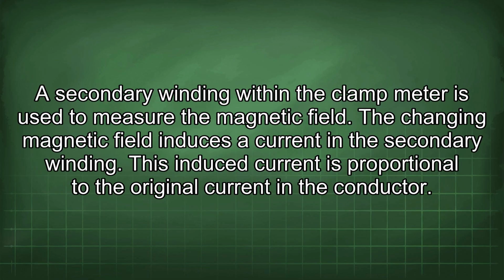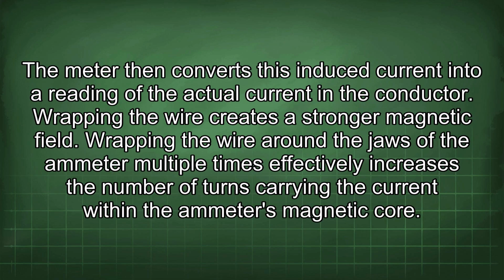A secondary winding within the clamp meter is used to measure the magnetic field. The changing magnetic field induces a current in the secondary winding. This induced current is proportional to the original current in the conductor. The meter then converts this induced current into a reading of the actual current in the conductor.